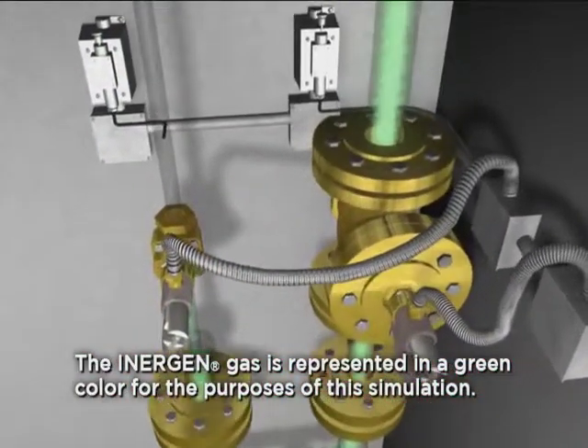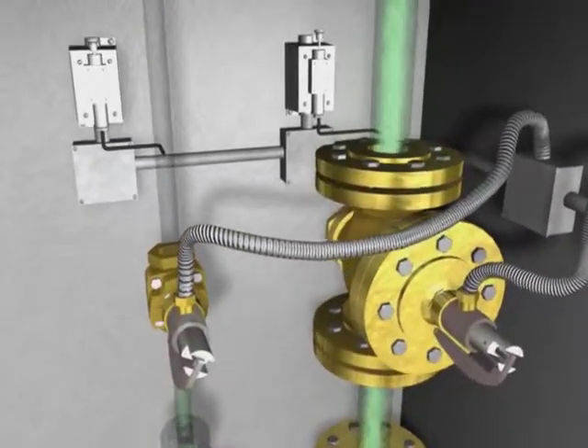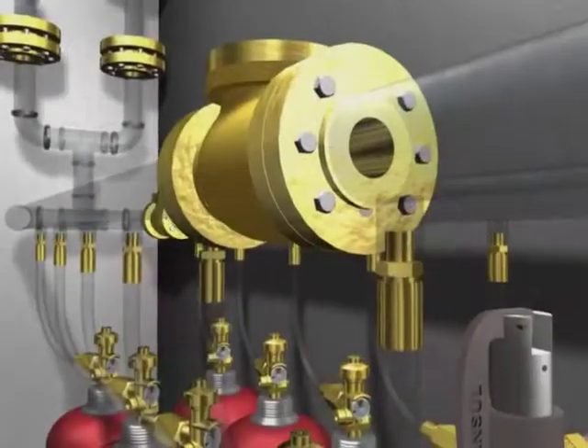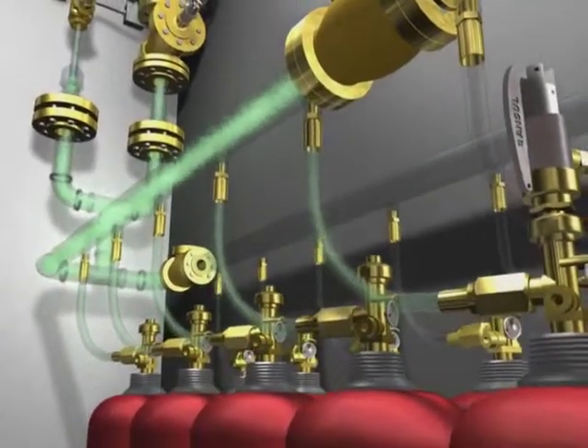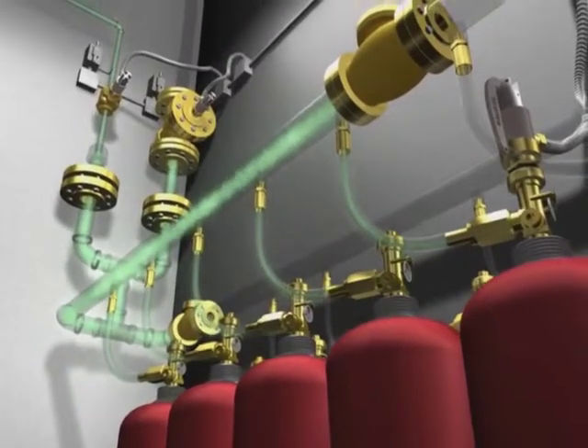In places where Inergen is protecting more than one room, a unique selector valve is used to direct the system discharge into the appropriate zone. A check valve is used in a selector valve system to separate the discharge of one zone from the other, by preventing the Inergen flow to the main system cylinders.